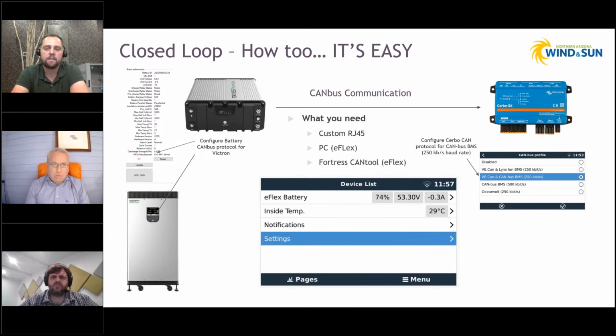This allows the batteries to provide accurate information and allows the system to optimize charging and discharging limits. This is hugely advantageous for us because we're often assisting in the commissioning process remotely. It gives us assurance that both the batteries and control systems relay accurate information, state of charge, gen start parameters, charging parameters, everything accurate with respect to the battery and inverter system. This is also advantageous to the end user, since they can see this accurate information. A shunt-based battery monitor, when configured correctly, can be fairly accurate, but any misconfiguration or miscalibration can cause misleading information.